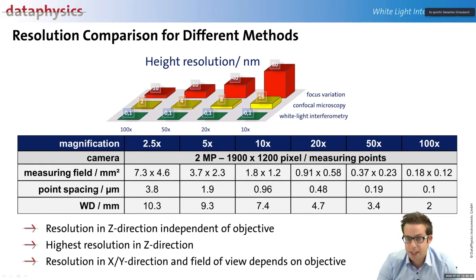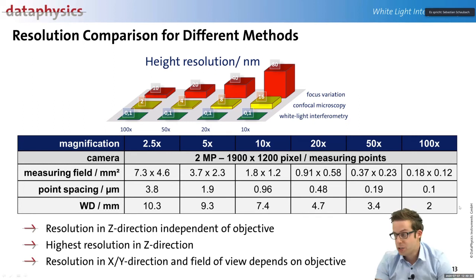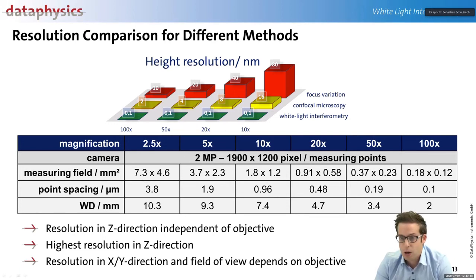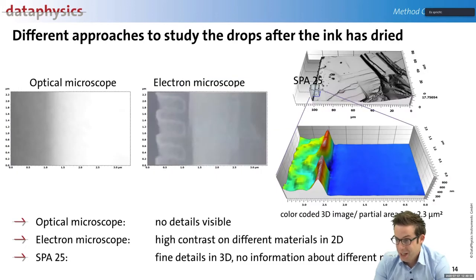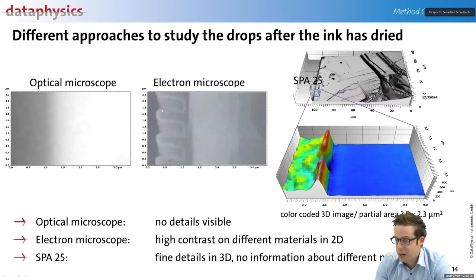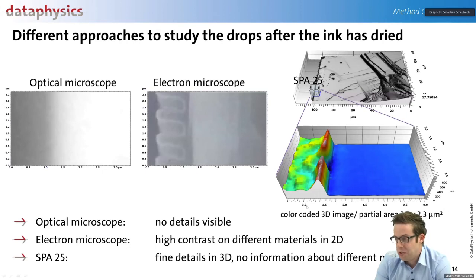The resolution in X and Y depends on the objective. Using a 100x objective gives around 100 nm point spacing in X and Y. With a normal 5x or 10x objective you get around 1 micrometer resolution in X and Y. Comparing technologies: with an optical microscope you see gray and white; with an electron microscope you see some structure; with the surface profile analyzer the whole thing becomes a three-dimensional model with very precise height information. We can generate a 3D map of such objects.